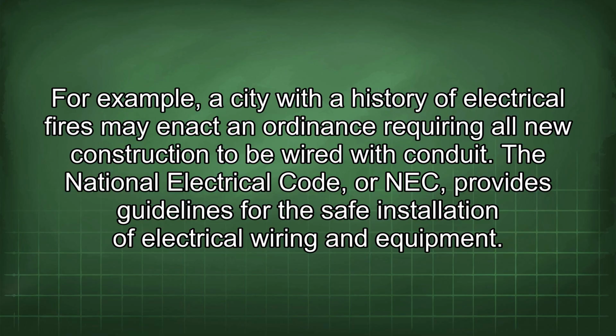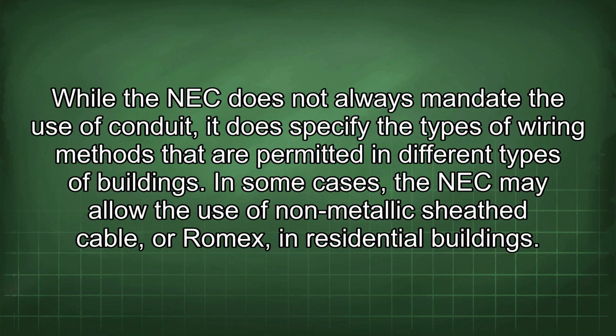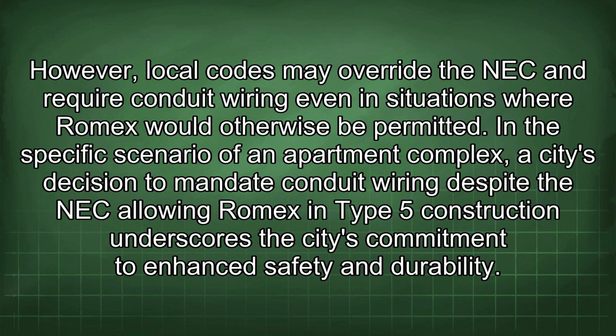The National Electrical Code, or NEC, provides guidelines for the safe installation of electrical wiring and equipment. While the NEC does not always mandate the use of conduit, it does specify the types of wiring methods that are permitted in different types of buildings. In some cases, the NEC may allow the use of non-metallic sheath cable, or Romex, in residential buildings. However, local codes may override the NEC and require conduit wiring even in situations where Romex would otherwise be permitted.